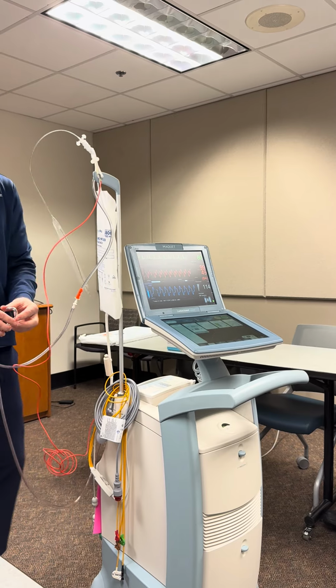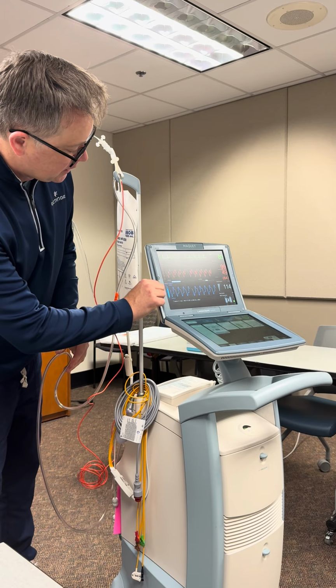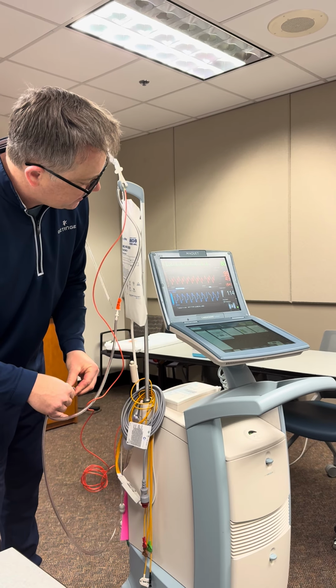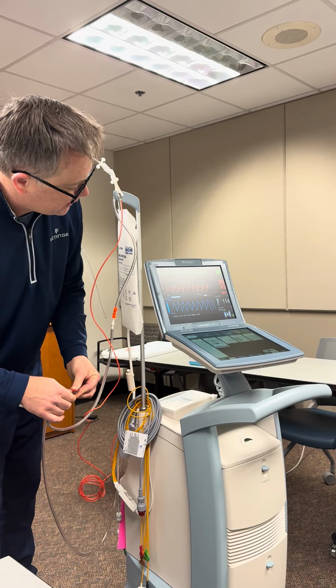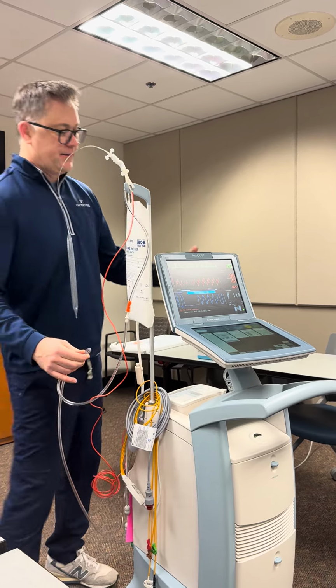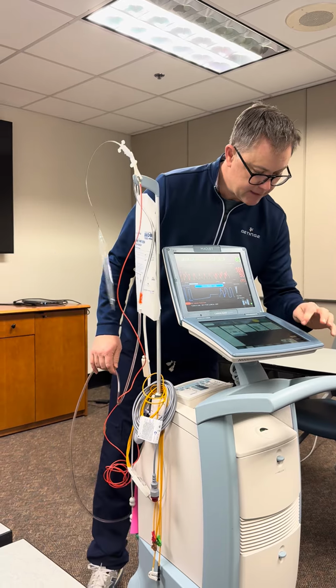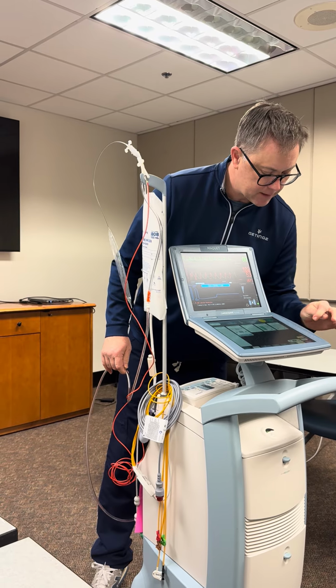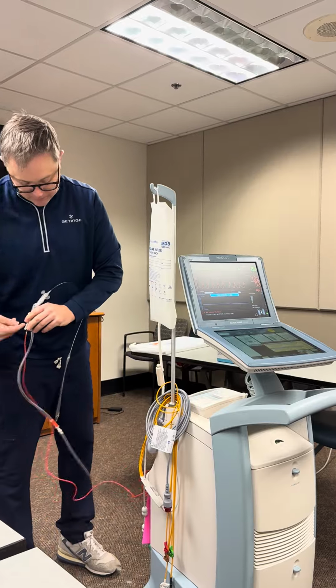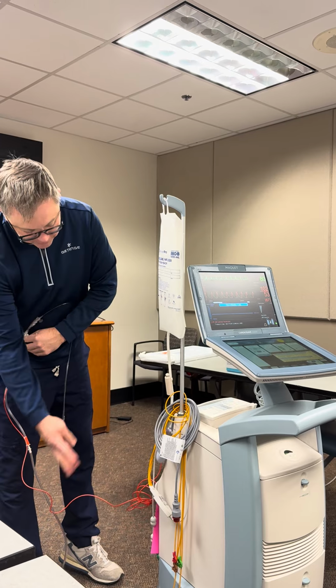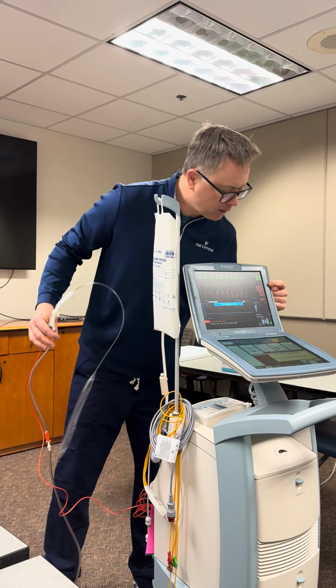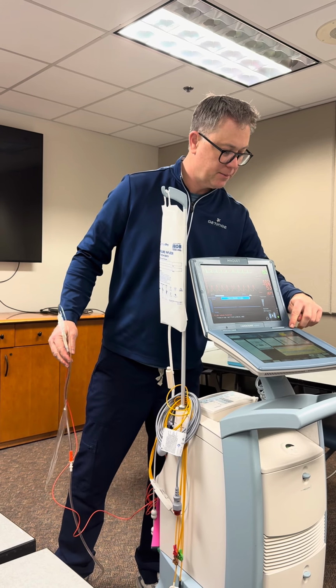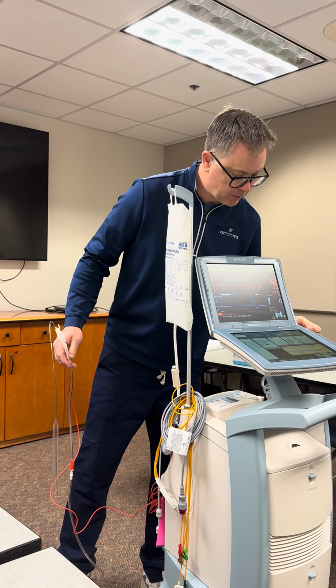Another one you might see is if you get a kink in your helium line. Watch what happens to our waveform here. We'll kink this off. It's going to be rounded off. I've got a kink in my waveform, and it's going to stop. Pause audio, help screen. It's going to tell me, hey, you've got a kink in your helium line. I'd go back, trace it, and clear it. And whenever you get a red alarm, you've got to come back in and restart the pump. So I'll restart it and then we're rocking and rolling again.